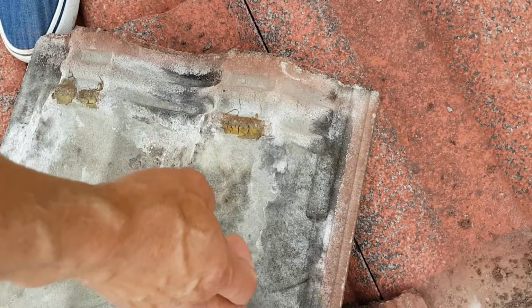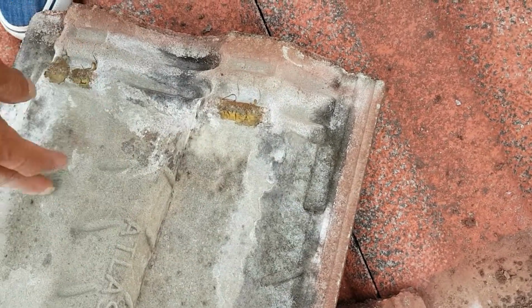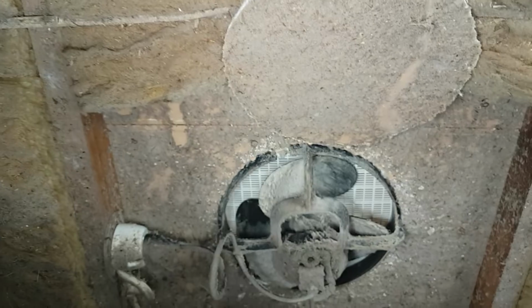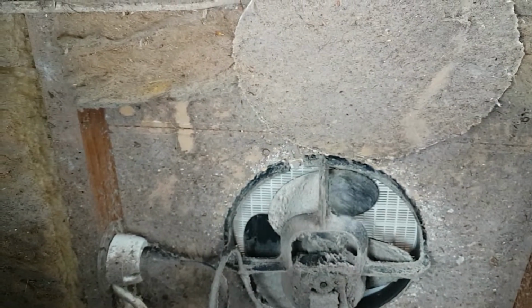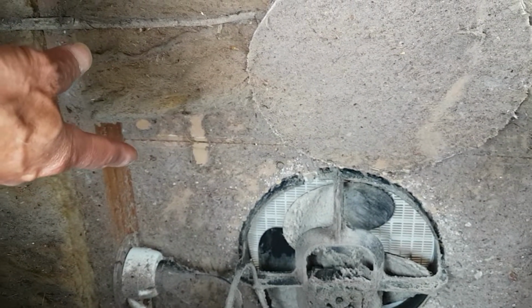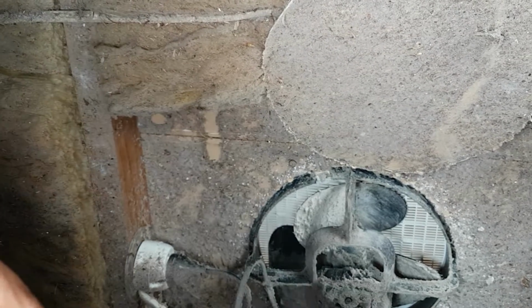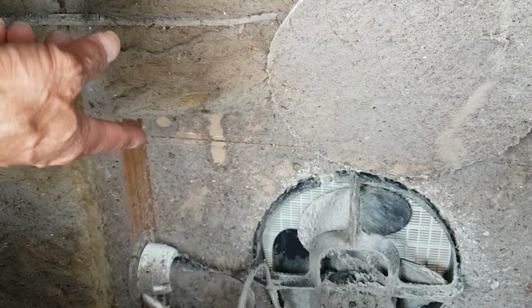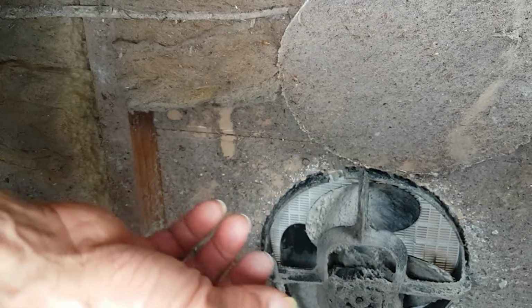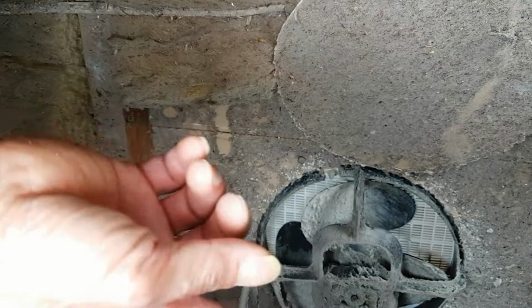And it's because if you look down into the ceiling cavity, you see the old bathroom exhaust fan. And what happens is that all the moist air gets pumped up into the ceiling cavity, hits the cold surface of the underside of the tile, and then condensation forms. And then it starts to drip onto the ceiling.